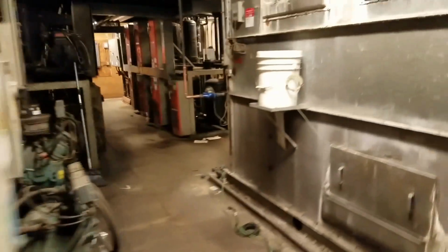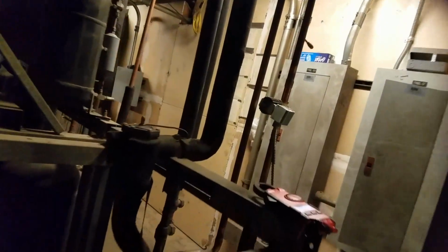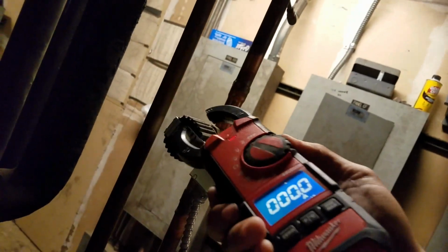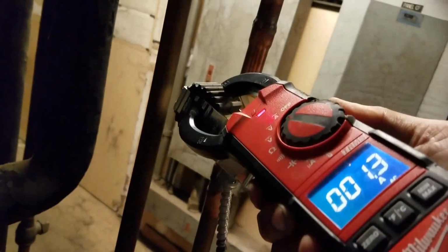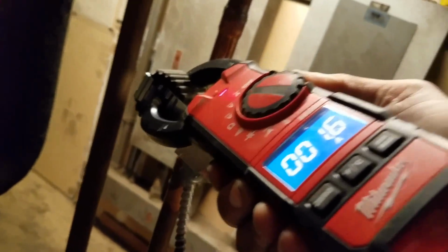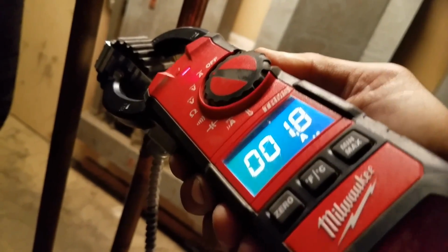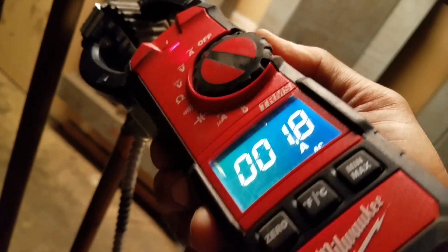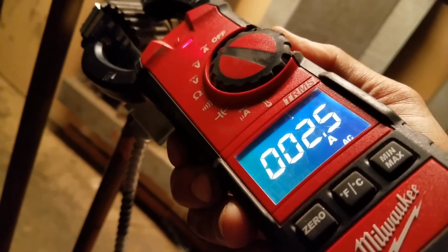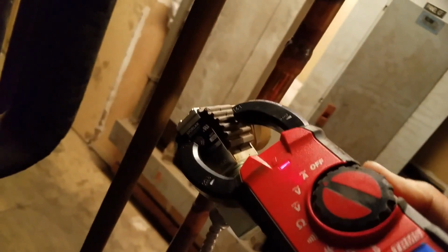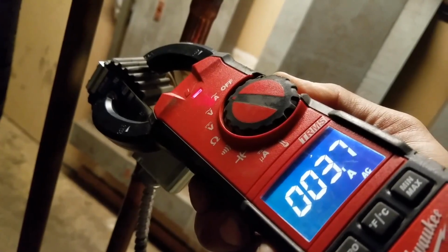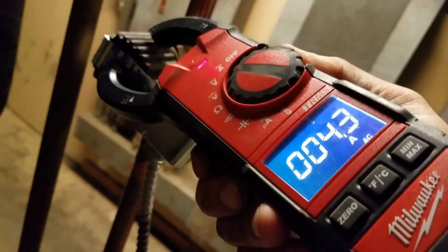So that's a good way to verify, to make sure that you did the right thing, was to run it through a full defrost. Remember guys, verify, it's very important. Always verify what you did. Don't just make the change and walk away. You always got to verify it. Okay, so there you go. I got amps on my solenoid. So it's back on.